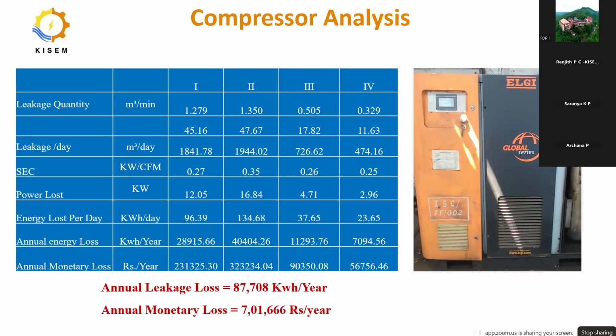For an equipment like a compressor, that much of savings will be there. I think 4 compressors are operating for the industry, so those 4 compressors will be contributing so much energy, and that savings will come to 7 lakhs with these actual settings and changing the pressure requirements. So these are the pressure reduction techniques and others.